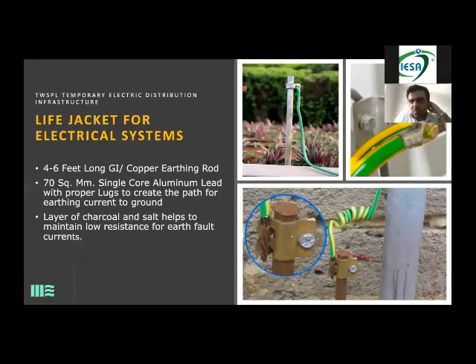Now, if by chance you touch an electrically charged box, what the earthing is basically doing is this: because your body has more resistance and the earthing has less, the electricity always takes the low resistance path. So ultimately it takes the path to the ground, not to your body. If the earthing is not there, your body will take those currents, like electrocution or electric shock. So again, the earthing system has to be done for each and everything which is coming on site.